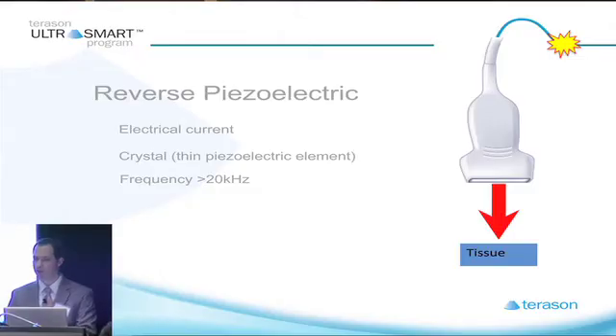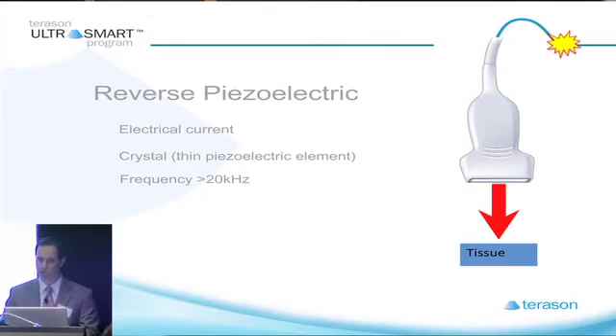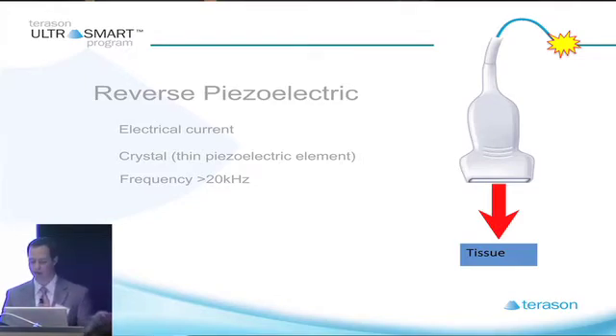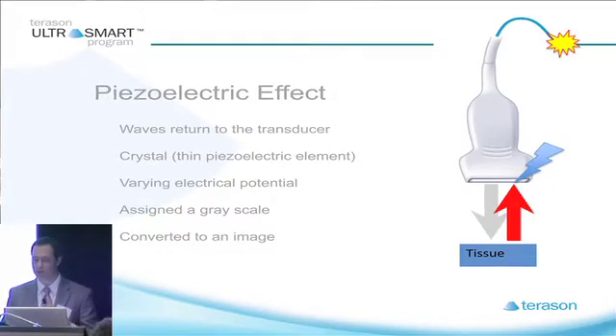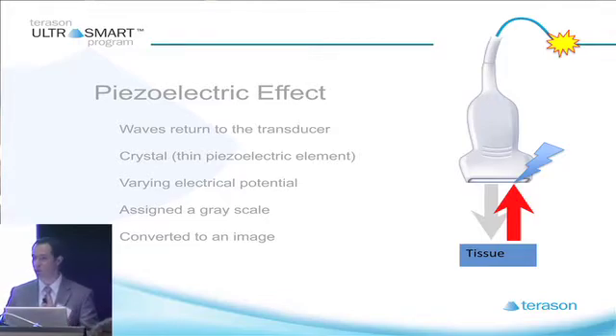The whole concept of how ultrasound is generated is by the reverse piezoelectric effect. Electric current flows down to the transducer and goes to a crystal at the tip of the transducer — a very thin piezoelectric element. That generates a signal of sound waves, and by definition, ultrasound waves are greater than 20 kilohertz.